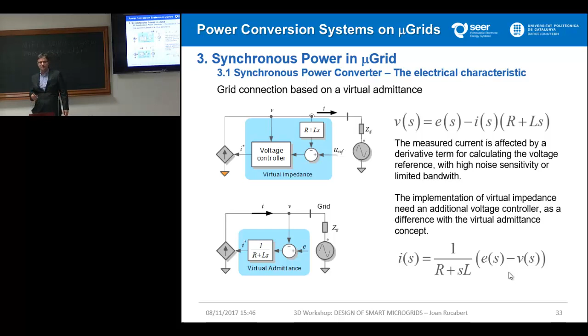This is the implementation of the synchronous power conversion. As you can see, this concept is just a control concept, so we don't have to change or modify in any way the topology, the power topology of the converter. It's exactly the same as what you get with your control. What we do is impose a voltage, comparing with a real voltage, and this voltage difference passes through the virtual admittance. This virtual admittance gives a reference, we give a current reference, and this current reference will enter the reference of the power converter that you can buy from any supplier. This is the reference that you are going to give to your power converter supplier.